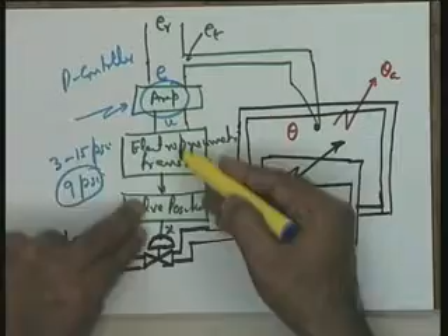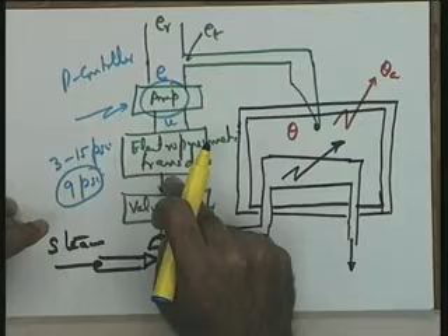And yes, please. So what is the theta A? Theta A is the environment ambient temperature. I am saying theta A is the ambient temperature, and this is actually theta A bar plus theta A. I am taking this theta A as the deviation of the ambient value from the value which was taken when the setting of the transducer and valve positioner was done. After all, when you were doing this setting, there was a heat loss then also, but then that heat loss has been taken care of by that setting. But this setting now takes care of the heat loss which was there only with respect to the ambient temperature then only. So, any variation in the ambient temperature will create imbalance at this particular heat interface, and therefore, it will require either reduction or increase of the steam flow rate and hence the heat. Is it okay, please?